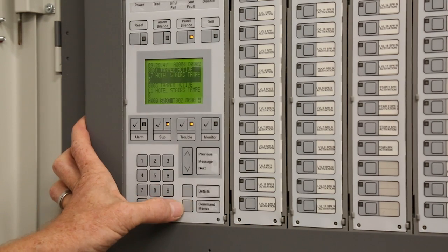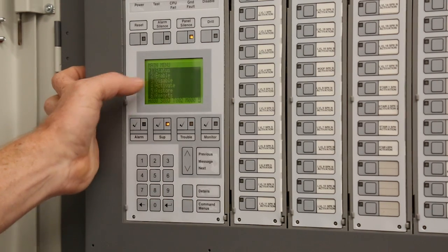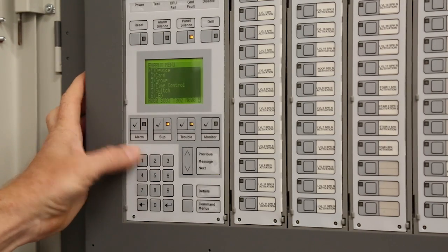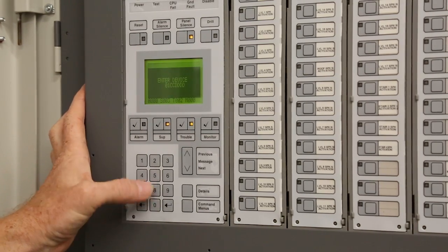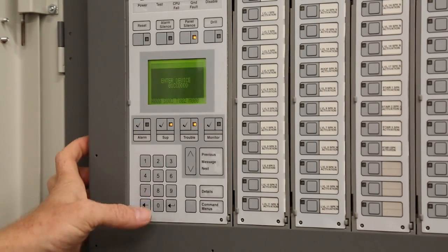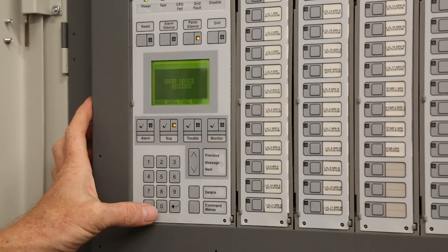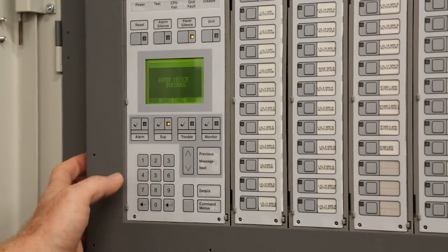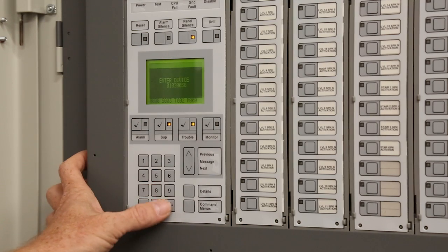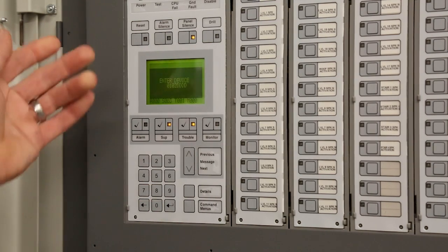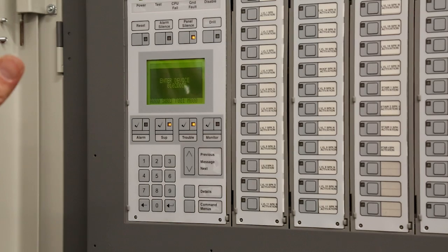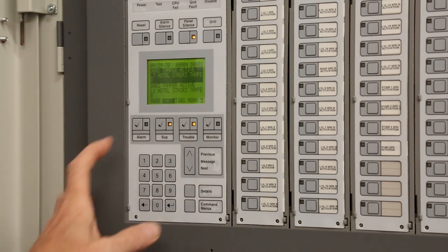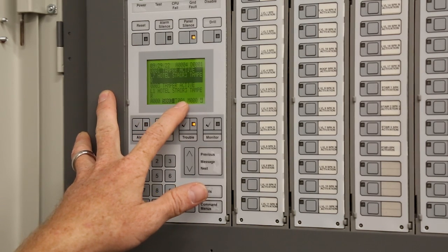To re-enable it again, just hit the command menu again. Go into enable, which is number 2, and it all prompts you on there. Device. And again, just put that number back in. Remember, you got to fill all the characters up. So if it's device or card 2, you have to put 02 in there. And then fill in the first 4. And then it was 38. Hit enter. Right now, it didn't ask for a password because that password's held in there for 15 minutes. So if you came back later on, you had to put the password back in. If you notice, we're back down to 1 trouble again. Okay.